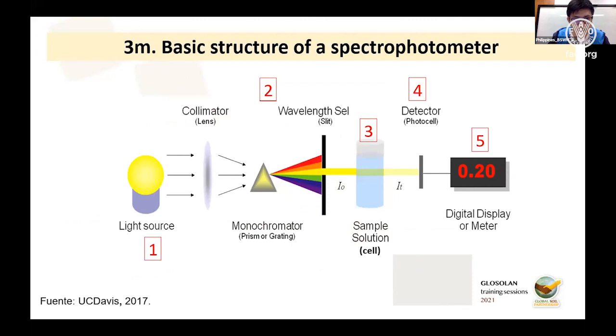The basic structure of a spectrophotometer is straightforward: there is a light source, a wavelength dispersive element, the sample solution through which light passes, a detector, and a digital display or meter. We measure the amount of light that passes through the solution, because the solution containing the complexes absorbs part of the light coming from the light source.